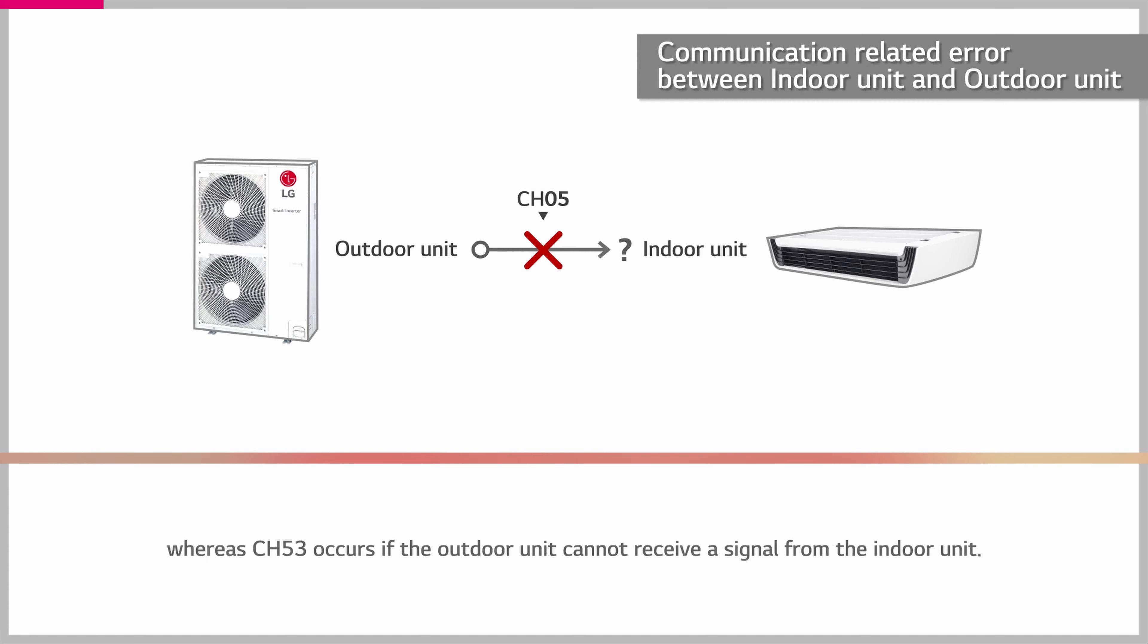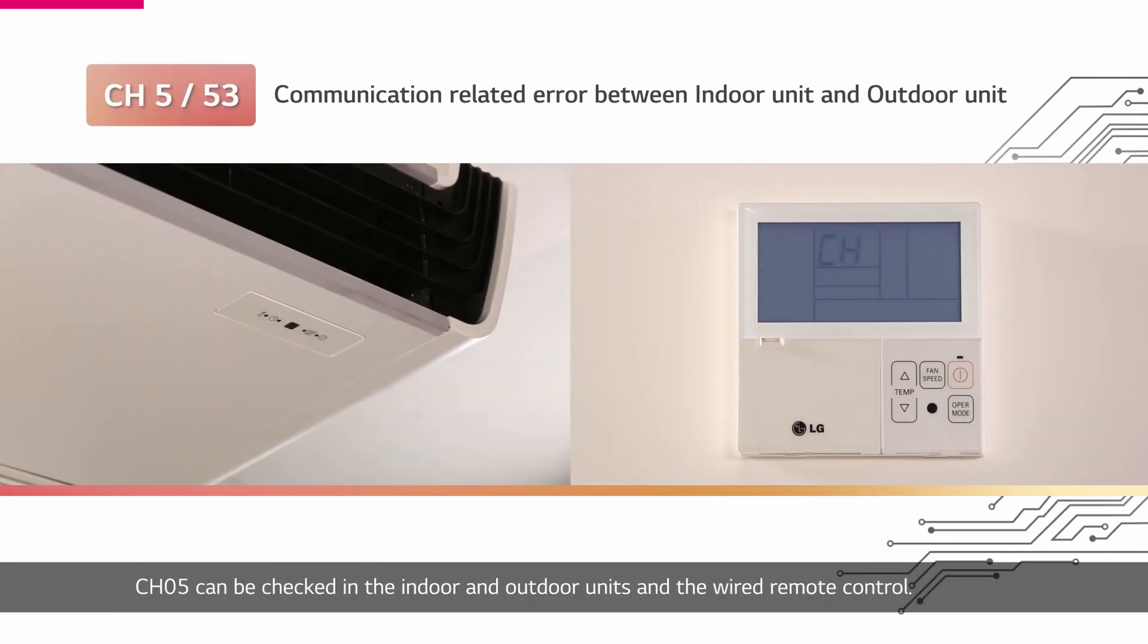whereas CH53 occurs if the outdoor unit cannot receive a signal from the indoor unit. CH05 can be checked in the indoor and outdoor units and the wired remote control.